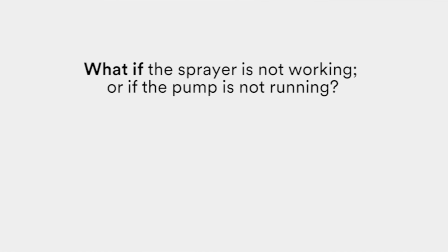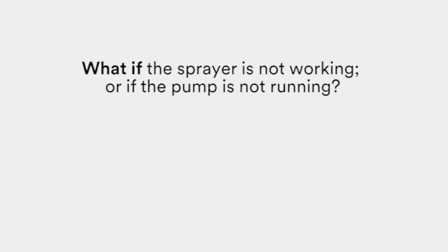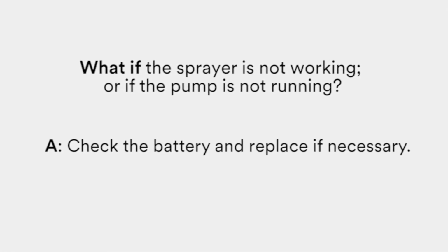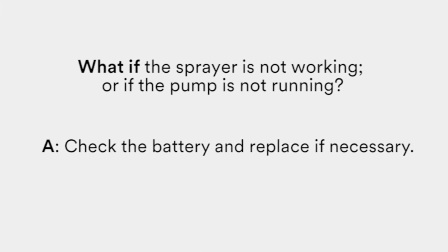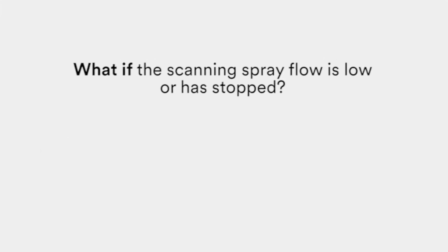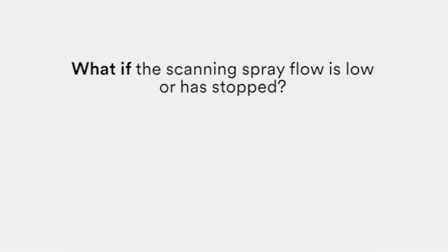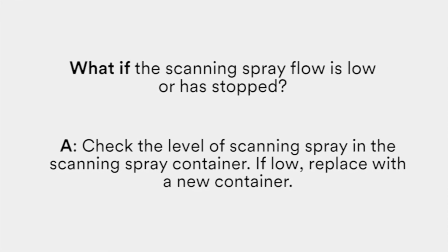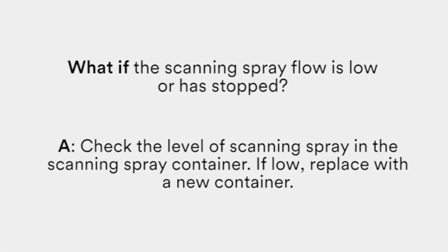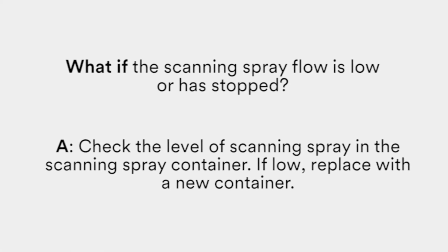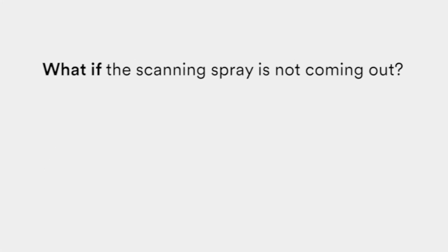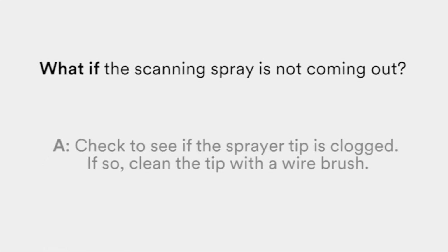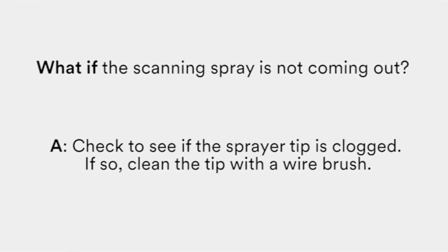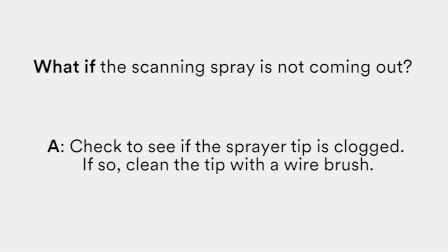Let's go over some what-if troubleshooting tips. What if the sprayer is not working, or if the pump is not running? If this is the case, check the battery and replace if necessary. What if the scanning spray flow is low or has stopped? Check the level of scanning spray in the scanning spray container. If it is low, replace with a new container. What if the scanning spray is not coming out? Check to see if the sprayer tip is clogged. If it is, clean the tip with a wire brush.